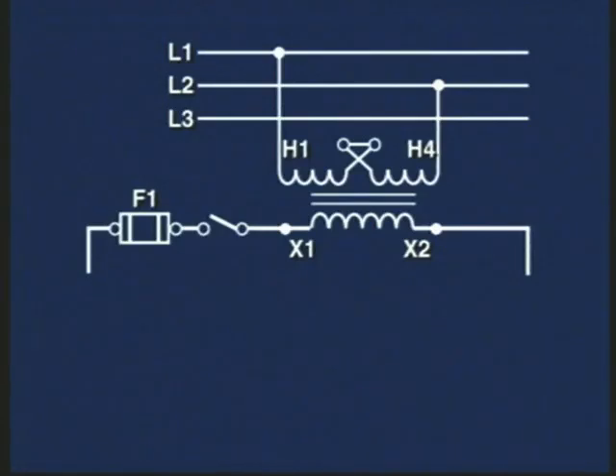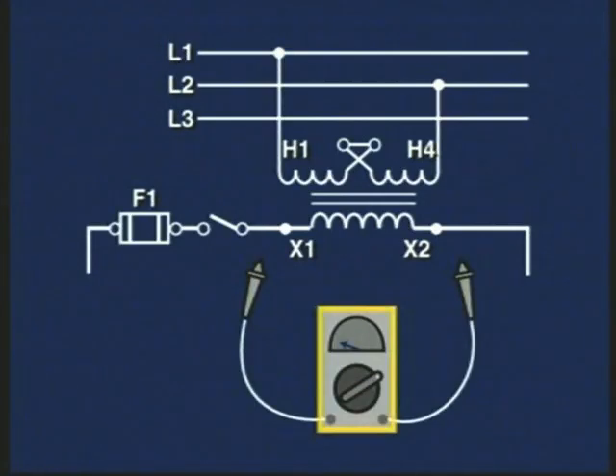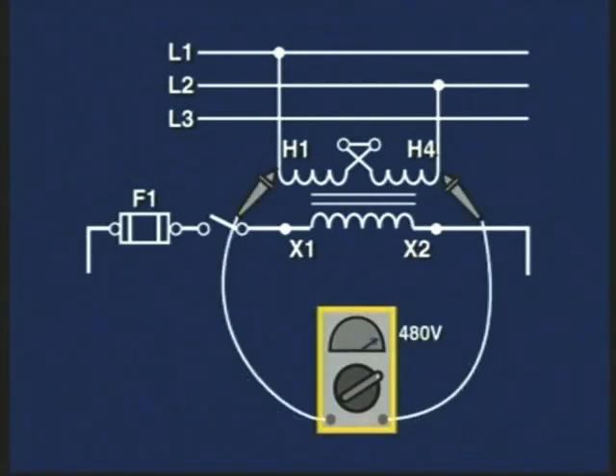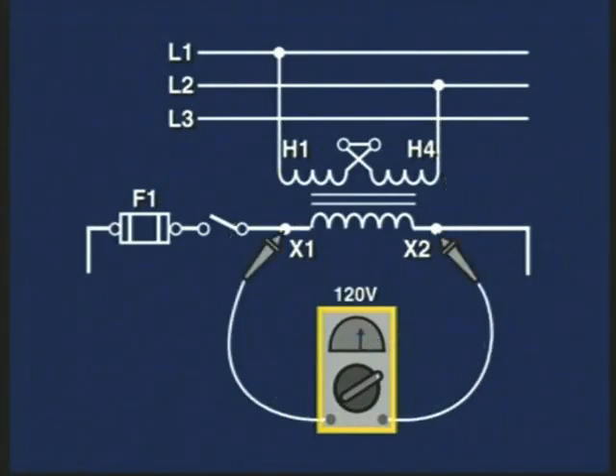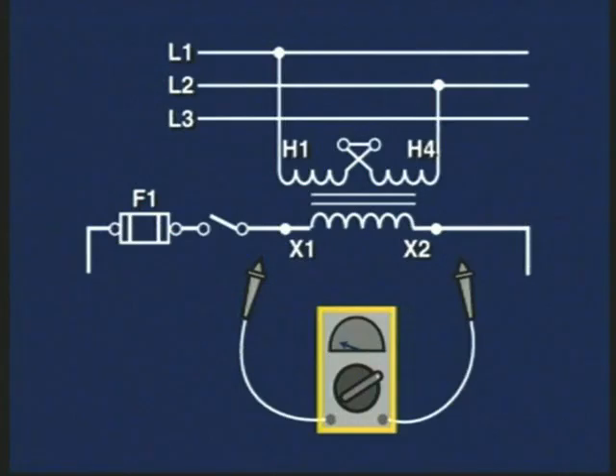First, we would check the incoming power to the primary of the transformer by testing the L1 and L2 voltage across the H1 and H4 terminals of the transformer. If the voltage is correct, in this case 480 volts, then we would check the secondary for the proper voltage across the X1 and X2 terminals of the transformer. If the voltages are correct, in this case 120 volts AC, the transformer is working okay. If not, the transformer is faulty and requires replacement.